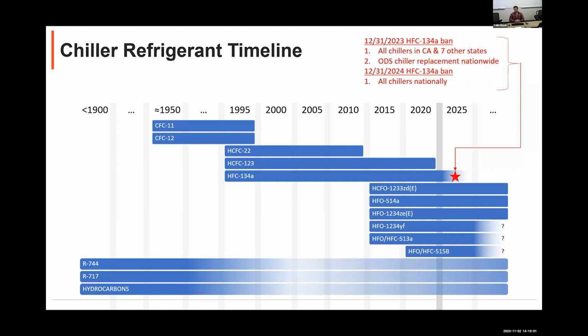The next generation of refrigerants means that there's a lot of change with equipment availability. So there's HCFO 1233ZD. That's a pure HFO with a global warming potential of 1. So that's going to be a long-term refrigerant option as far as we can tell. HFO 514A is an HFO blend, but it's a blend of 2 HFOs. So it still has a global warming potential of 2. And just in case you're not familiar, for comparison, HFC 134A has a global warming potential of 1,300. So these other refrigerants are more than 1,000 times less global warming.